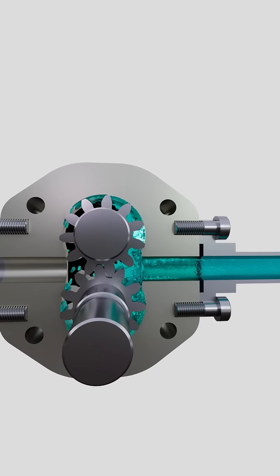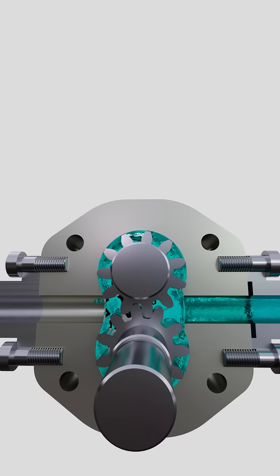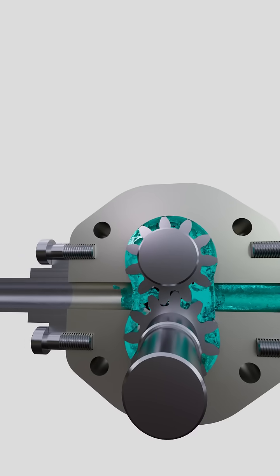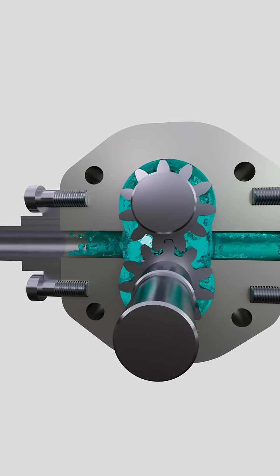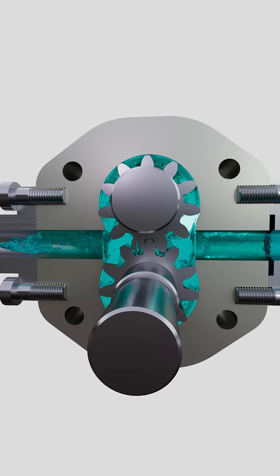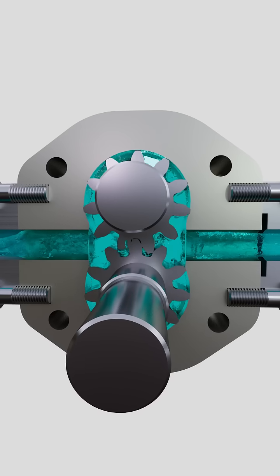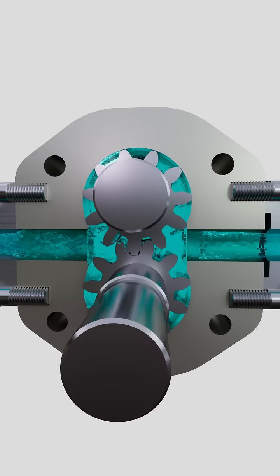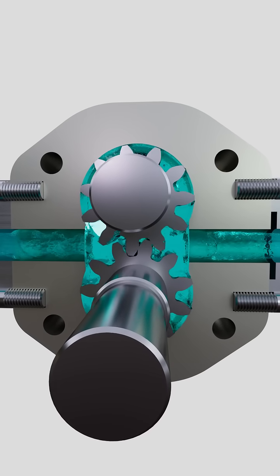In the place where the gears disengage, there is a free space. It is filled with fluid from the suction pipeline. This fluid is trapped in the cells between the teeth and the casing. It moves to the area where the teeth re-engage.